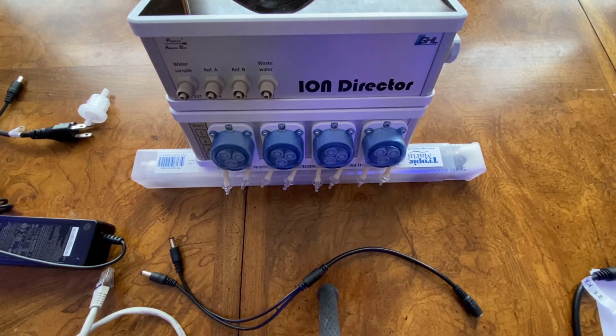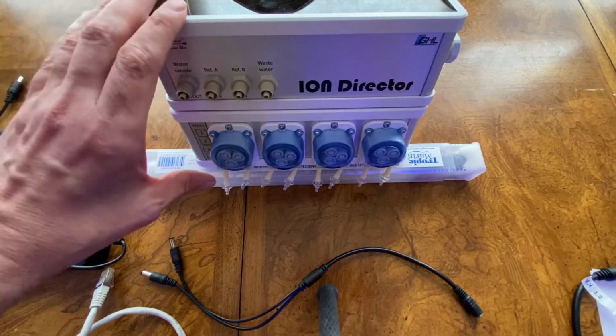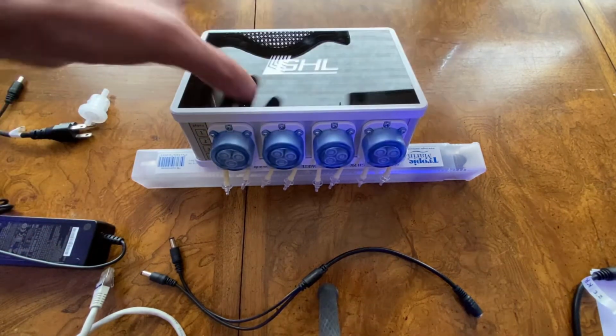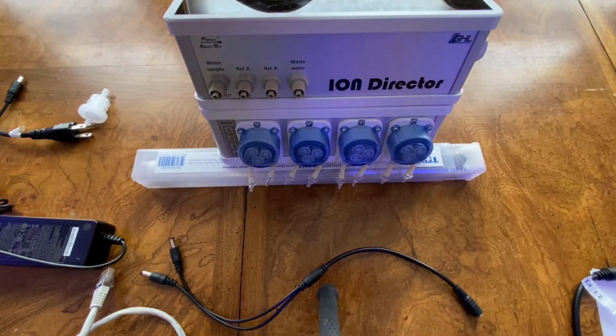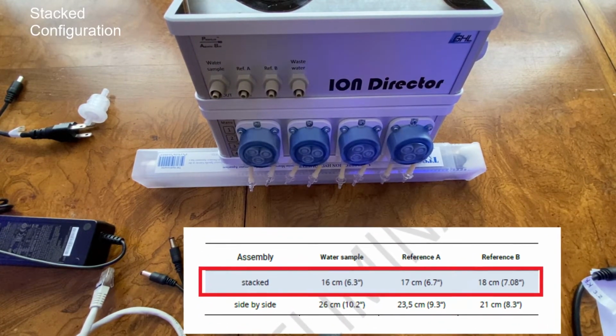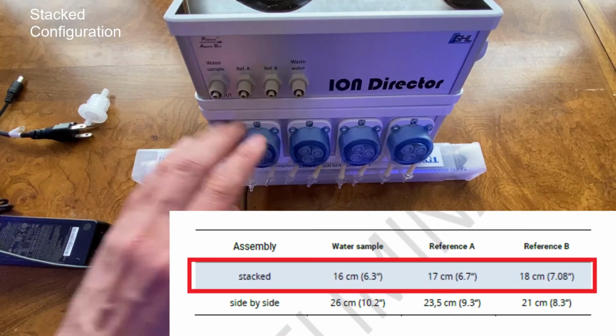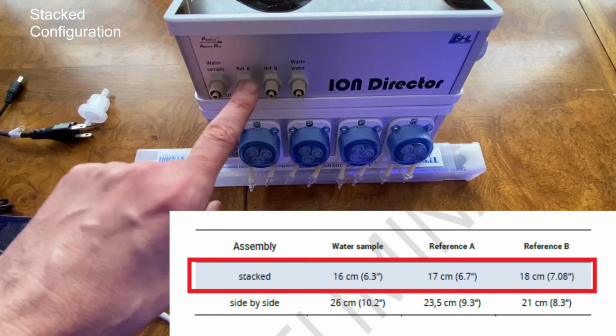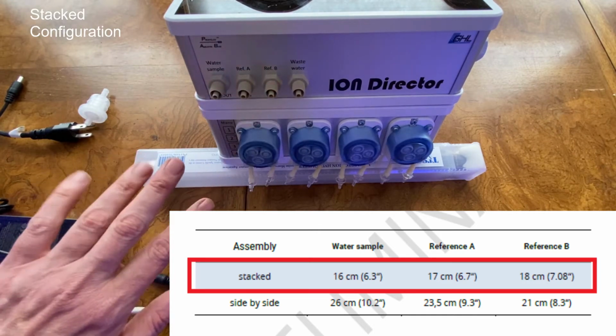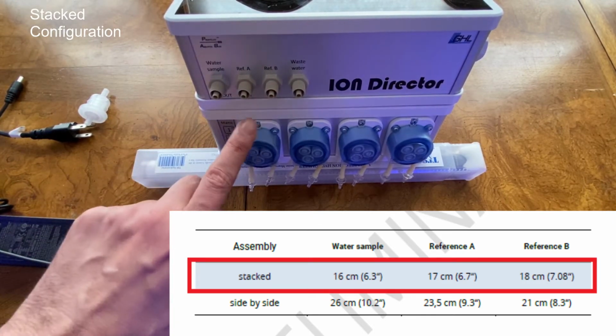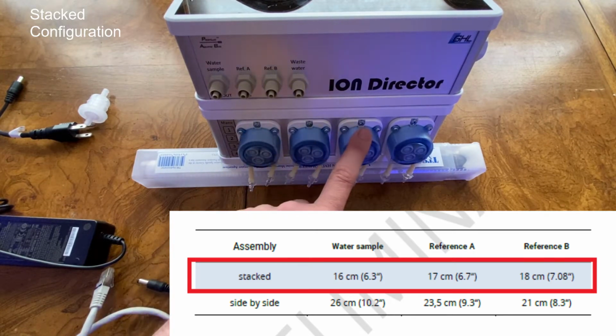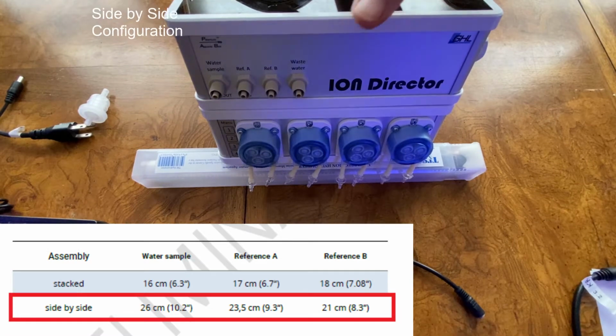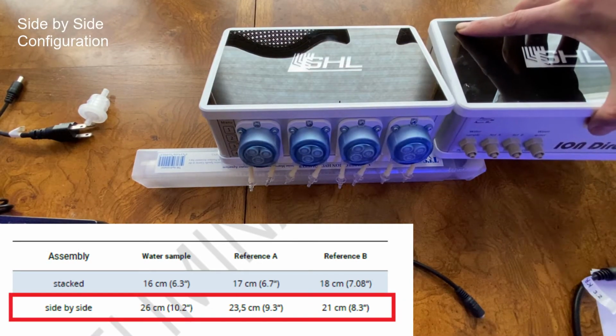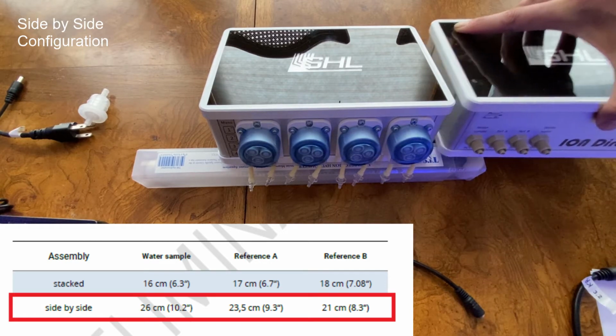Because of my setup, I am going to be doing this type of configuration, which is a stacked configuration, and not this configuration, which is a side-by-side. Now that I know that I'm going to be doing a stacked configuration, using the reference chart as shown here, I know what size I need to cut my dosing tubes for the connection between the Ion Director and the doser that's going to be supplying the Ion Director with the appropriate water sample, reference A and reference B solution. So I now know what the length of the tube is going to need to be from my water supply, my reference A, and my reference B pump. Very important: if you go with this type of configuration, the tubes are going to be longer, and again, you would use the appropriate chart and cut them to that length.